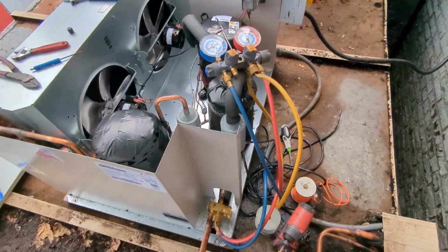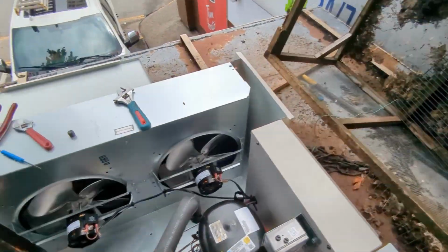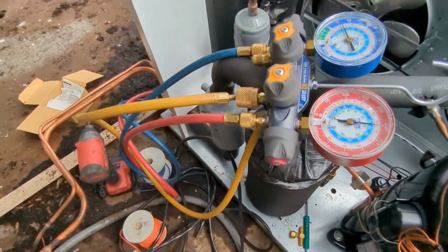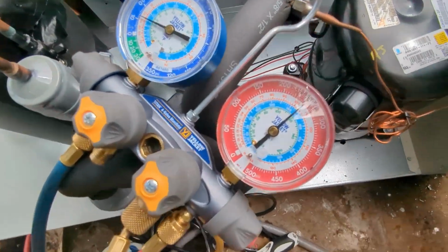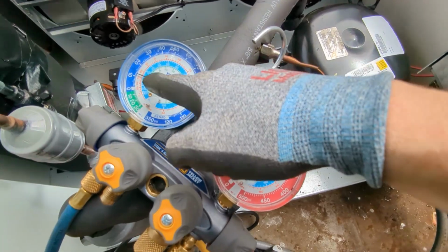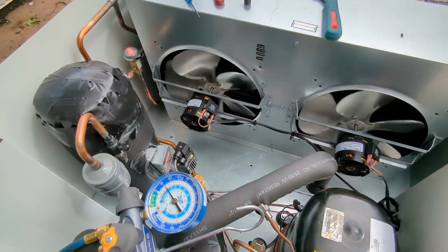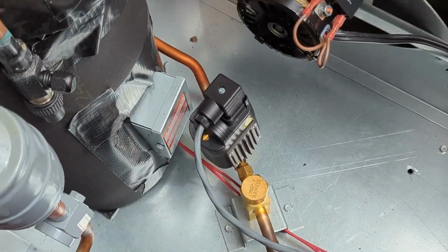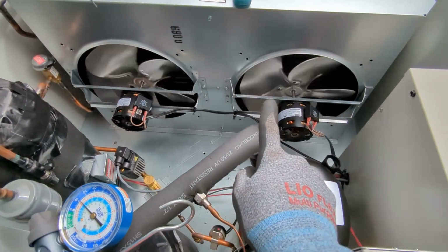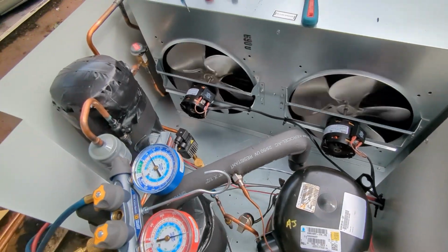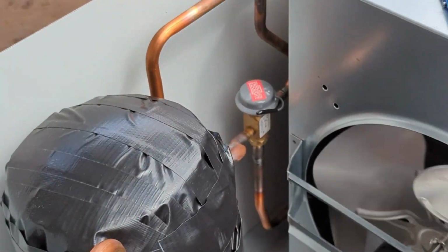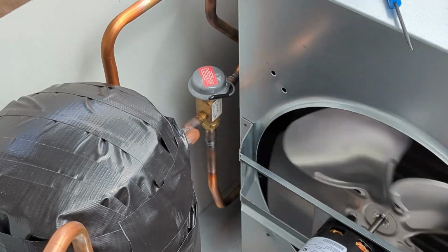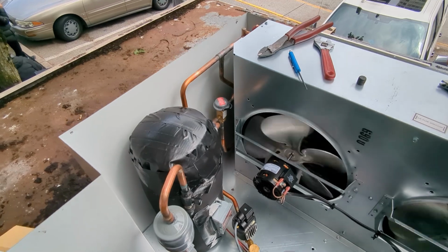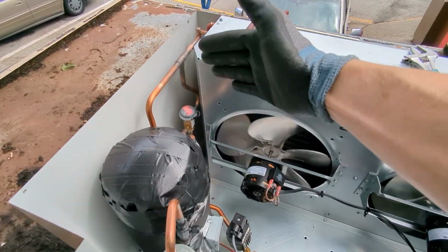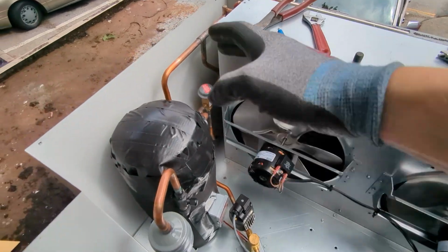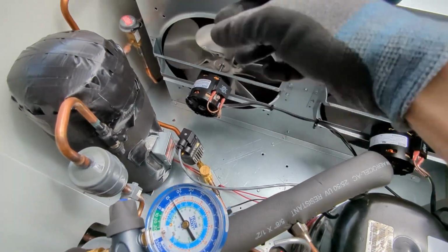Dad just went to grab a coffee, so I'm gonna try to explain what we just did. Yesterday our pressures just weren't coming up, we had really low suction pressure, and when we arrived today it was like 8 or 9 psi. So we've installed a fan speed controller, which makes the condenser fans run as slow or as fast as needed. By doing that, we're basically bypassing the low ambient control, which is that valve there, which I think is what was giving us trouble yesterday. It seemed like all of our pressure was hanging back behind that valve. Now it's free flowing because of the fan speed controller.